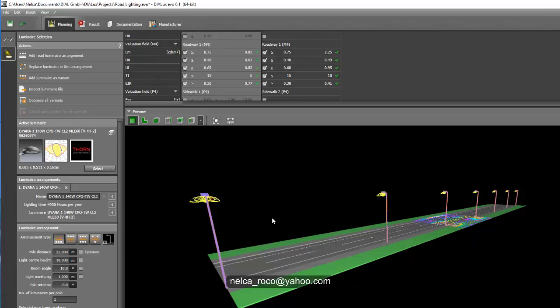So it depends. If you divide 1000 by 25 meter spacing, how much is that? You will have 40 poles and 40 luminaires now compared to the 100 before. So I think for the contractor side, it is very good. Actually, it's very good. If they compare it, we have previously 6 meter high pole, but this time it is 10 meters high, they will now check if the 10 meters compared to the 6 meter has a huge difference in pricing.